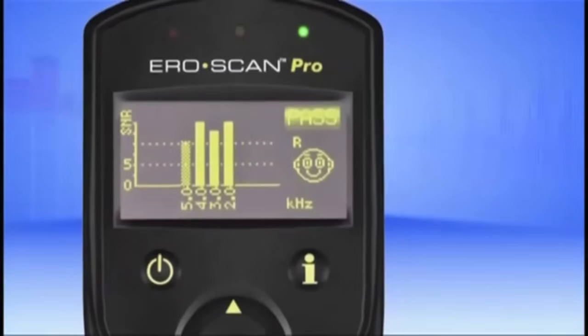This is an example of the DP-OAE test result screen. Let's go over this in detail. Each frequency used in the test is indicated by one vertical column. The number of columns shown will vary depending on the protocol you selected. The signal-to-noise ratio, or SNR, of each frequency is shown by the vertical axis. The height of each column represents the value of the SNR for that particular frequency. For example, if the column goes to the top of the display, then the SNR value is 15 decibels or greater. A solid yellow column indicates that the SNR pass criteria for that particular frequency was met. A darker hashed column means that the pass criteria was not met.